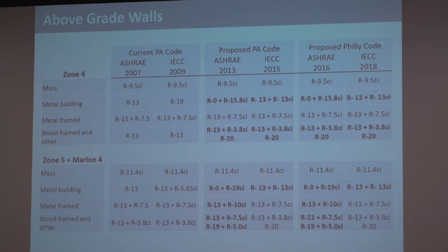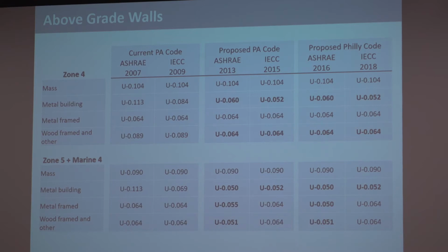value equivalent. And similar to all the other things, there are tables in ASHRAE that will help you figure that out, so you can look up wood frame construction at 16 on center and find your batts and figure out what the U value equivalent of that assembly would be. So yes, there's always mixing and matching allowed.